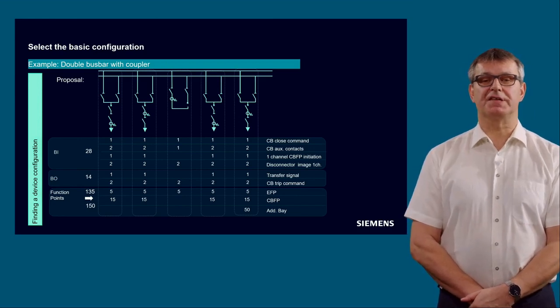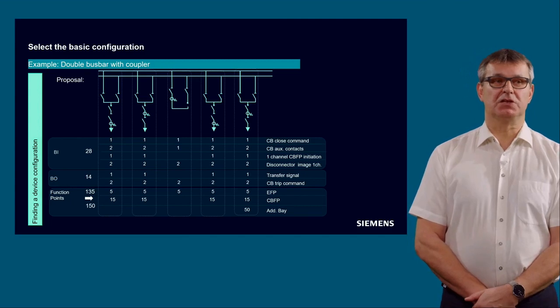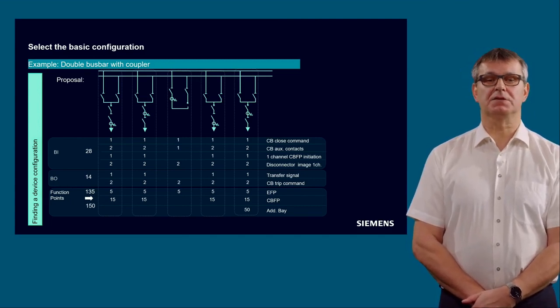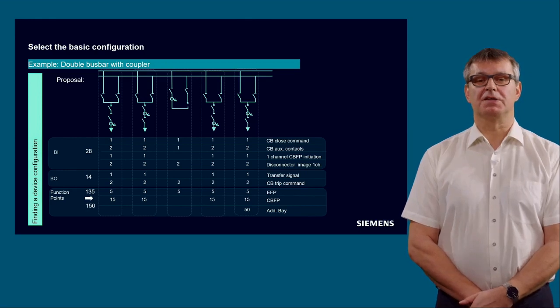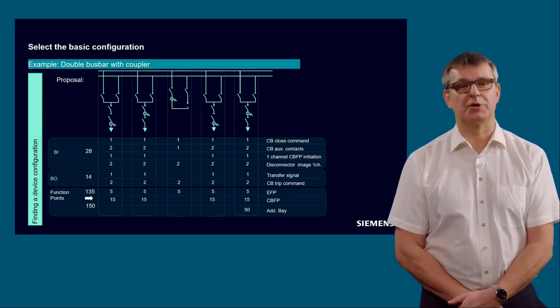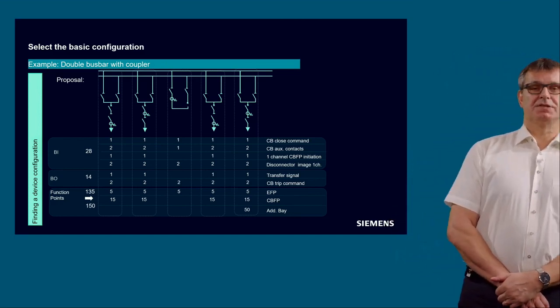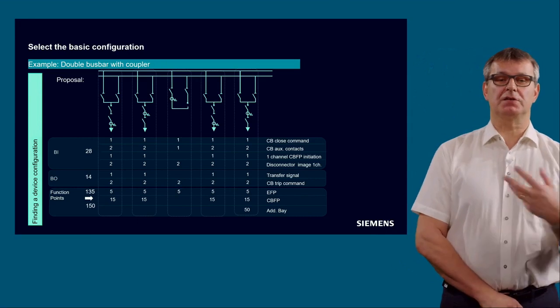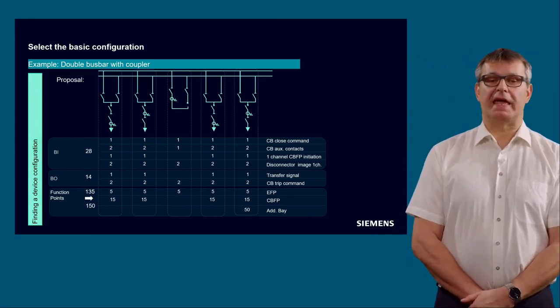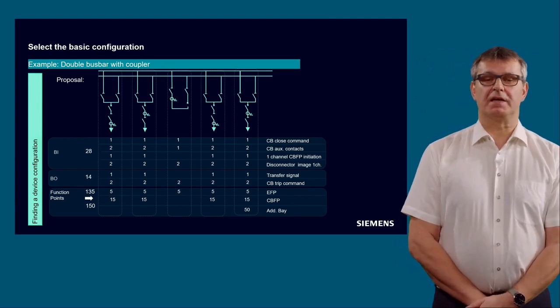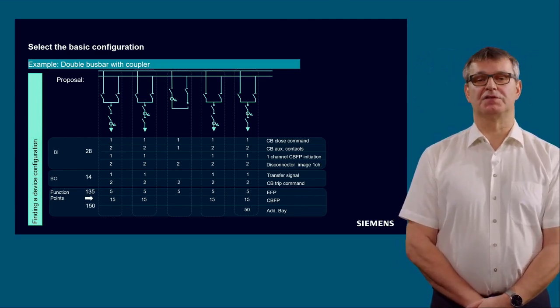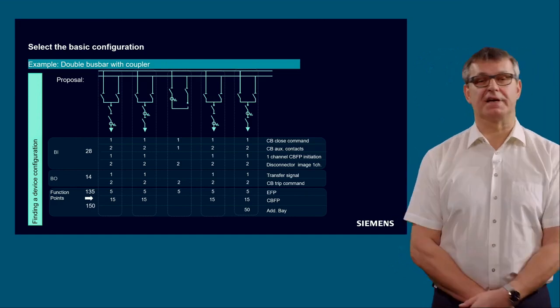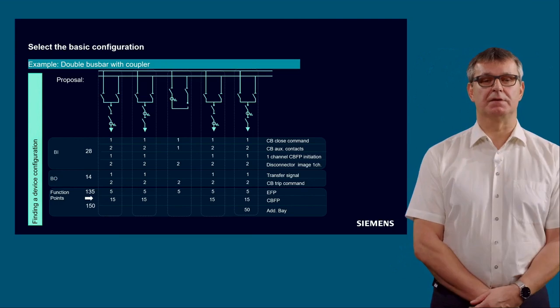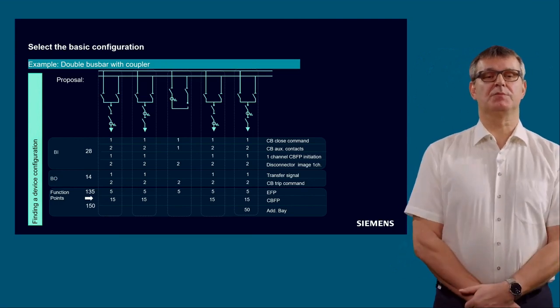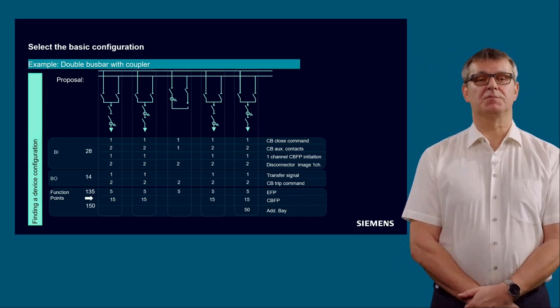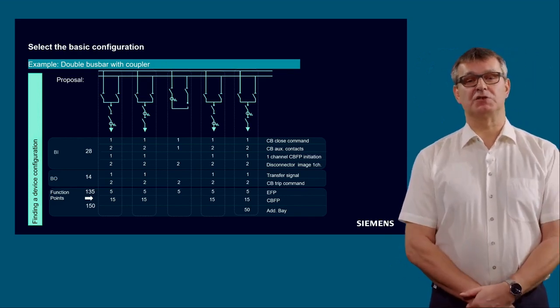Function points, already said. End-fault protection in each feeder and also in the coupler. So 5 points here in the sum. Circuit breaker failure protection. Here we assume only a 3-pole circuit breaker failure protection. This means 15 points in each feeder, no function points in the coupler. And for the additional bay, we need 50 function points for this 1 additional bay. Already 4 bays are included, as you remember, with significant feature B. So in total, 28 binary inputs, 14 binary outputs, and 135 function points.